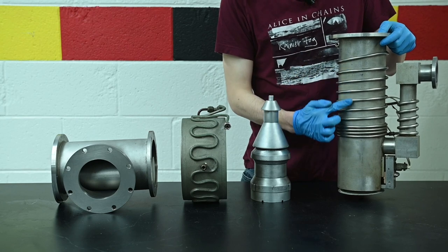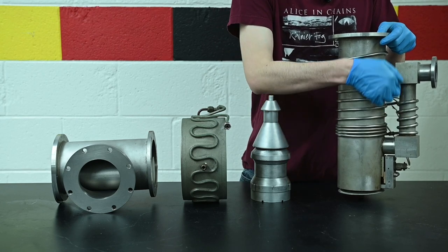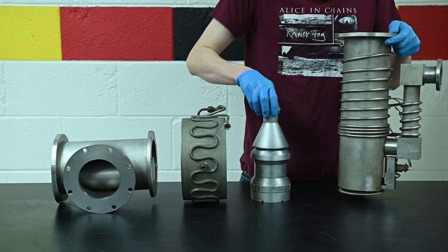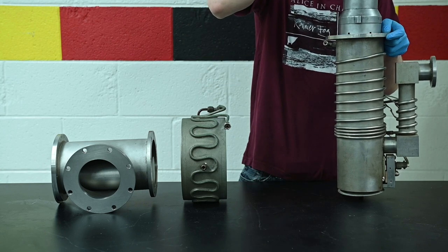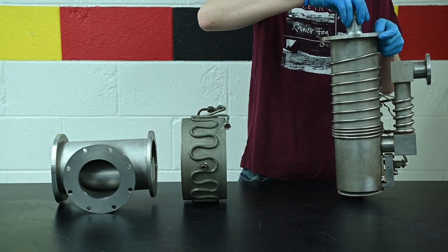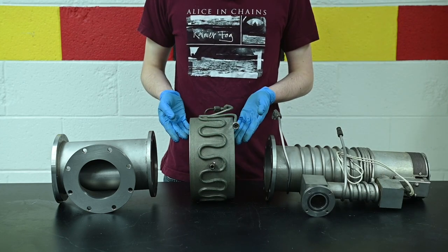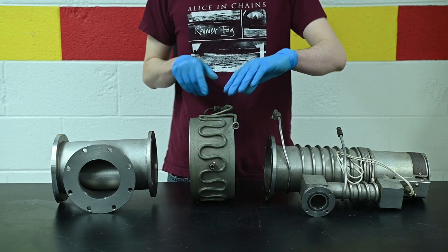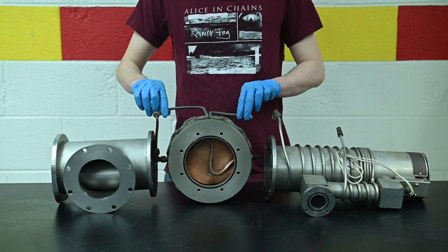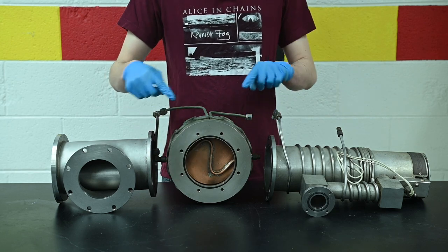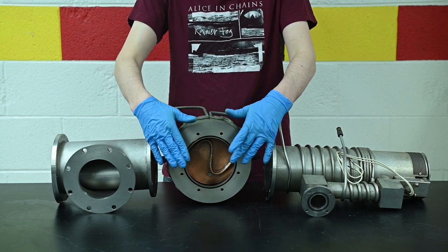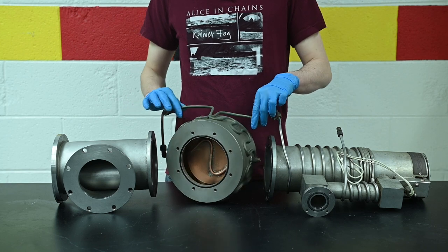The outside of the diffusion pump is jacketed with cooling tubes to recondense the oil vapor as it makes contact with the external surface of the pump. Above the top of the diffusion pump is the water-cooled baffle. The water-cooled baffle blocks any line of sight from the oil vapor to the vacuum chamber so that no backstreaming oil vapor makes its way into the chamber.